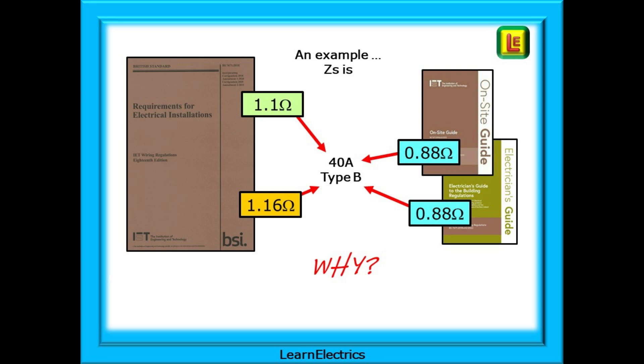Let's just take any example, a 40 amp type B breaker for instance. In the brown regs book we have two values for ZS for the same breaker, and then the on-site guide and the electrician's guide show a third value. Why is this and what's going on?